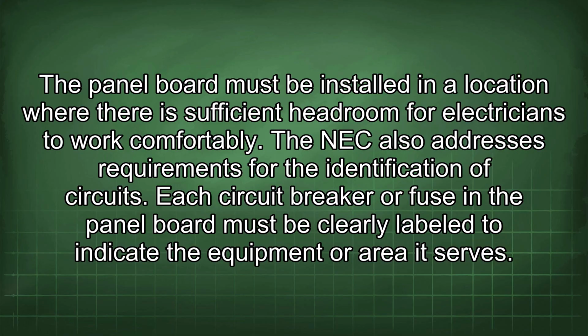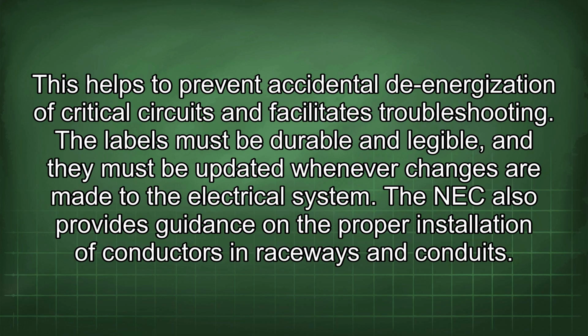The NEC also addresses requirements for the identification of circuits. Each circuit breaker or fuse in the panel board must be clearly labeled to indicate the equipment or area it serves. This helps to prevent accidental de-energization of critical circuits and facilitates troubleshooting. The labels must be durable and legible, and they must be updated whenever changes are made to the electrical system.